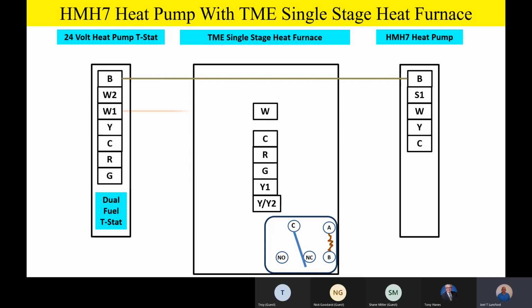Because this is a single stage furnace, we don't have a W2 input. So on our thermostat, we're going to take W1 from the thermostat to just plain old W terminal on the furnace. And by the way, the furnace has hard physical screw terminals. So W1 from the heat pump thermostat to W on the furnace, because it's a single stage furnace, to W outside, so we can bring on the furnace during defrost from the outdoor unit whenever we go into defrost. That Y terminal is going to go outside just like it did before from the thermostat to the outdoor unit.